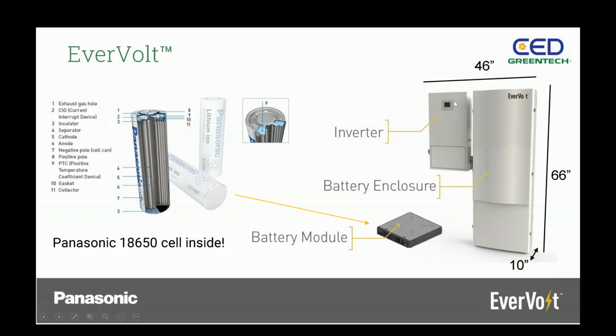The basic design of the system: you'll see we have an inverter and a battery cabinet. As mentioned earlier, it's a very slim profile. The cabinet is 10 inches deep, roughly 66 inches tall, and the two combined are about 46 inches wide. You can place the inverter on the opposite side or lower, or in various positions. You still have to stay within roughly 6 or 8 feet of the battery cabinet, but there is some flexibility there.